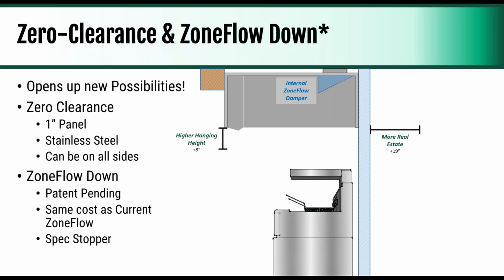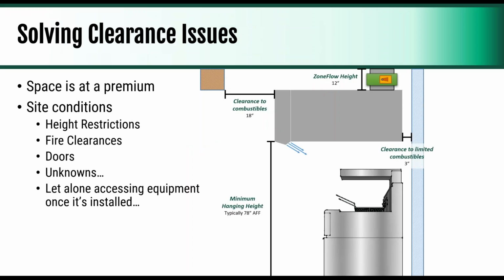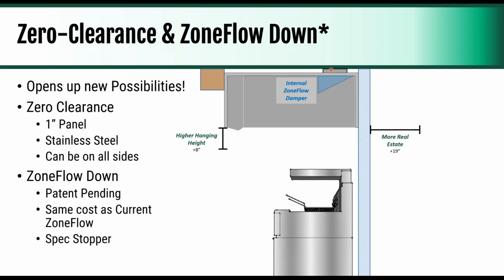And then the second thing we did: on the previous slide, you'll note this has the demand control zone flow dampers on. Those take up about 12 inches on top of the hood. What we did was engineer an internal zone flow damper that can go inside of the hood. That allows us to get that headroom back, but also to modulate all of the hoods so that you can have multiple hoods on one exhaust fan.